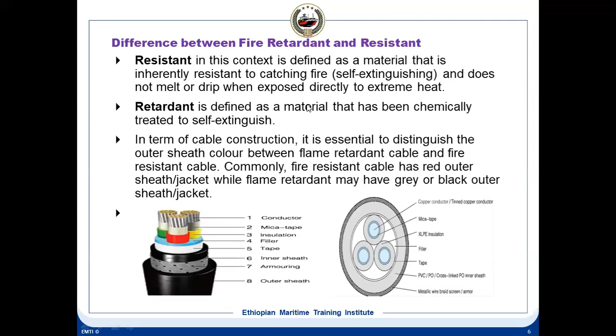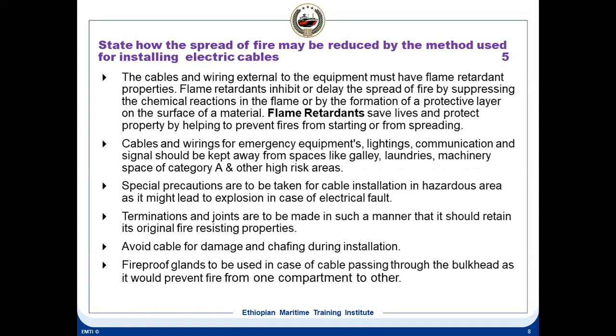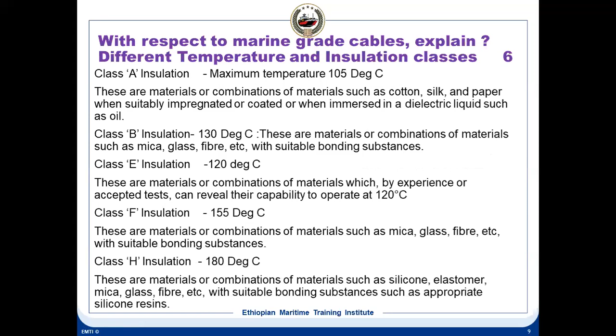Okay, so this is about the cable revision questions. I have told you all these four questions. First, in case of an electrical fire, what are the hazards associated with the electrical cable insulation? Then what are the remedies? Then the difference between flame retardant and fire resistant cables. Then how the spread of a fire can be reduced by installing the electrical cables. Then temperatures and insulation classes of the cables. And what are the commonly used insulating materials? Very important question: silicone rubber, XLP, ethylene propylene rubber, butyl rubber. Then what is sheathing? Why do we need sheathing? What is the purpose of sheathing? What are the sheathing materials used? Okay. With this, the cable part is finished. And then we will go to the next topic.